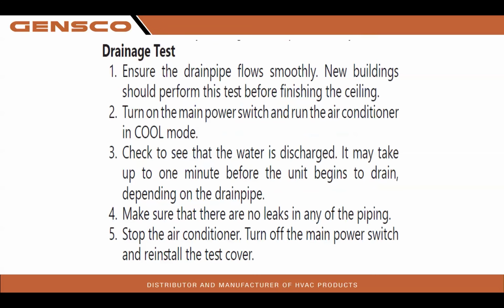Drainage test, we're going to make sure that our condensate drains are flowing correctly. We do have a P-trap. I know that on some installations I go to on site visits, there is no P-trap. Always, always, always put a P-trap on your installations.